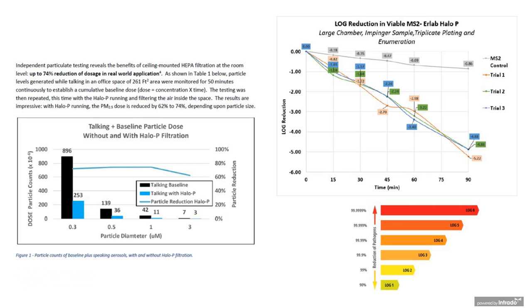Then you want to test the overall log reduction and the efficacy of a system when it's put in a controlled chamber and you inundate it with a pathogen or an MS2 virus. You want to see how long it takes to actually start getting a log reduction, and over the time of the testing, when do you achieve a 4 log reduction, which is a 99.99% reduction of pathogens.